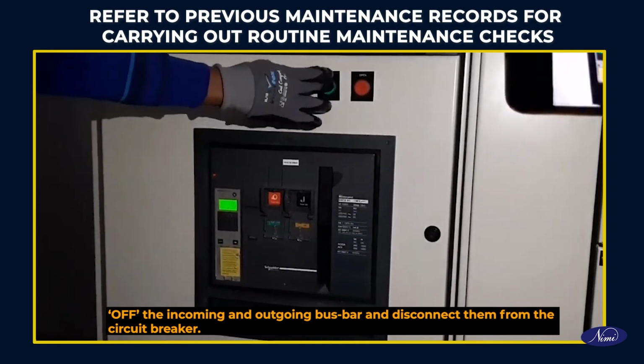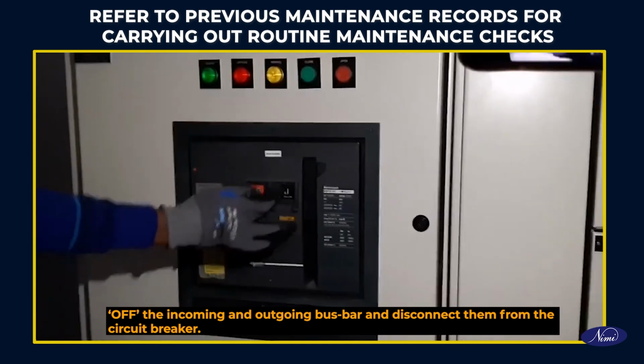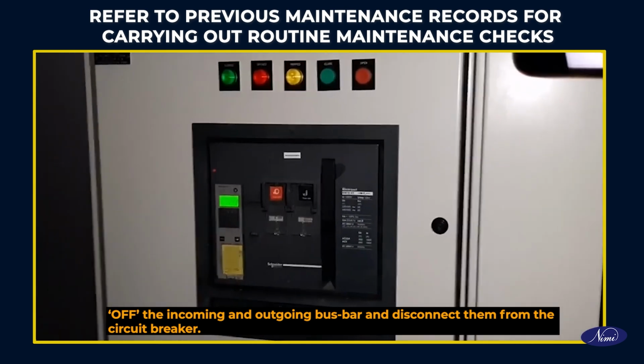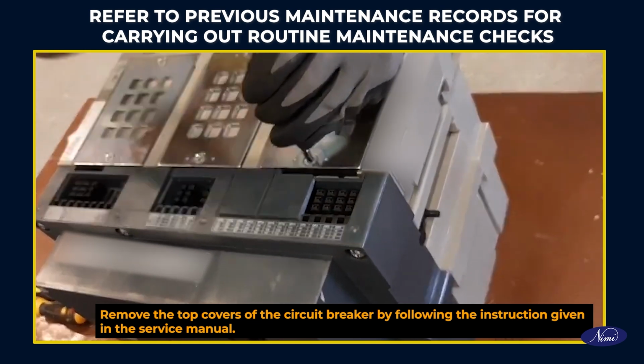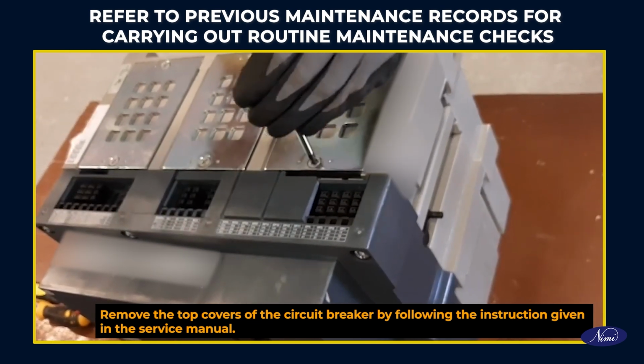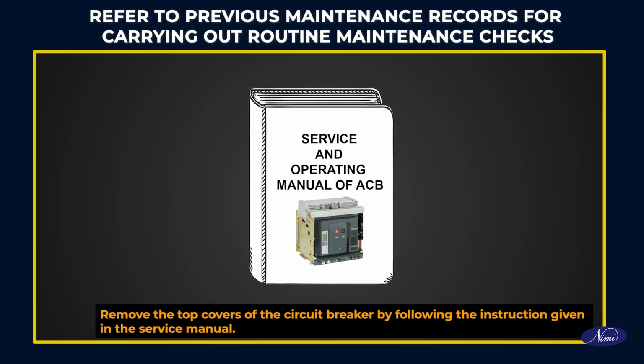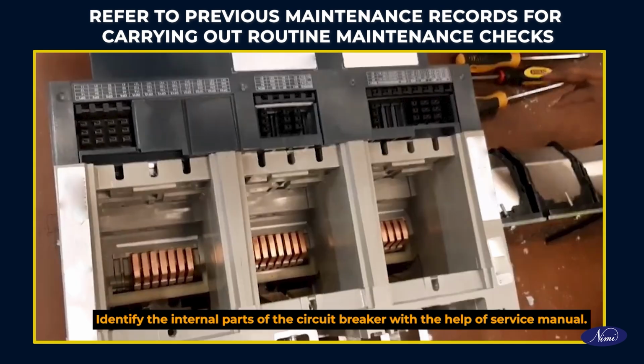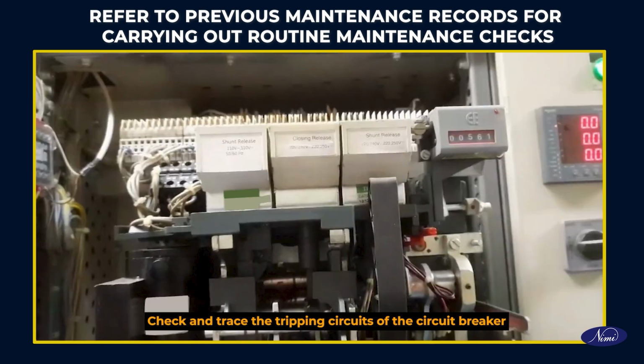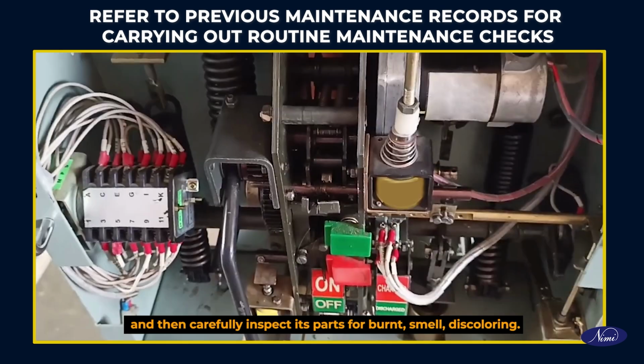Switch off the incoming and outgoing bus bar and disconnect them from the circuit breaker. Remove the top covers of the circuit breaker by following the instruction given in the service manual. Identify the internal parts of the circuit breaker with the help of service manual. Check and trace the tripping circuits of the circuit breaker and then carefully inspect its parts for burnt smell, discoloring.